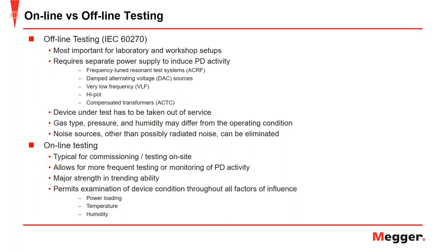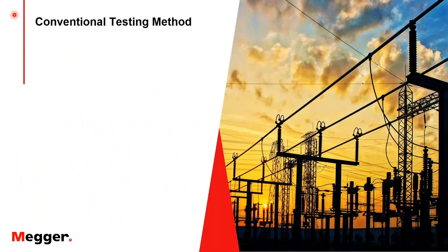When we talk about online testing, this is typical for commissioning and testing on site. This typically correlates to the unconventional methods and allows for more frequent testing or monitoring of partial discharge activity. And online testing offers a major strength in the ability to trend measurements and make comparisons based on prior measurements. And unlike the offline testing, online testing permits examination of the device throughout all the factors of influence, such as power loading, temperature, and humidity that you may not get when performing offline testing. Moving from that, we'll start talking about the conventional test method.